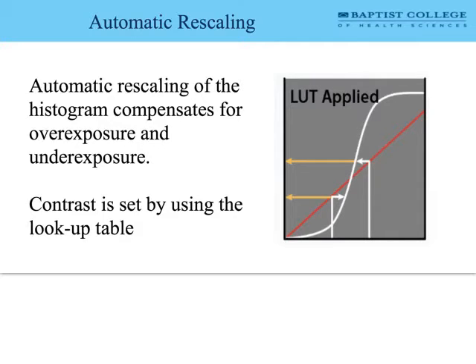As technologists, we are responsible for maintaining standards that limit patient exposure and must look for sources other than the displayed image to detect dose creep. The computer uses a lookup table to perform automatic rescaling, similar to the H&D curve from chapter 10. When the computer initially gets the data, it would demonstrate just a flat line of exposure values, but it automatically rescales and generates a contrast curve, changing the numbers until we get appropriate contrast in our image. Automatic rescaling compensates for overexposure and underexposure, and contrast is set using this lookup table.